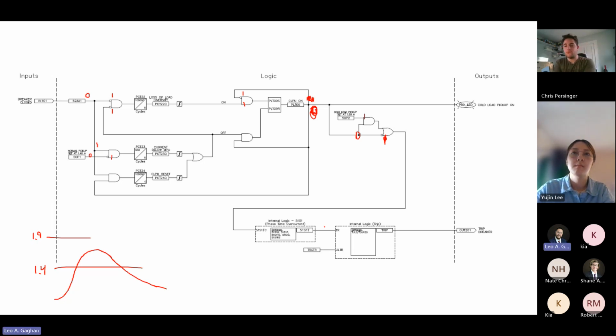And then the last part to this is, what if we close that breaker back in and there was a fault, and we've got this higher pickup that we can't see because it never normalizes, right? It's an actual fault rather than load. Well, we've got a 15-minute timeout here. So regardless of if it normalizes or doesn't normalize, this thing can only be active for a certain period of time before it resets itself. So, yeah, I guess a little bit of tricky logic, but I think pretty cool logic.